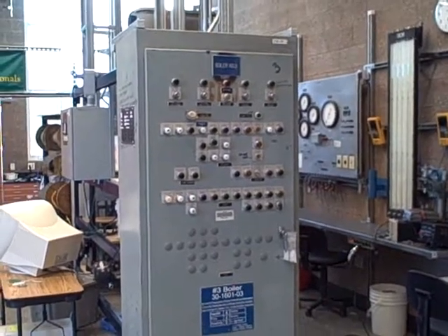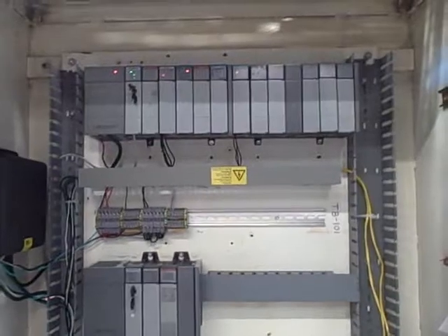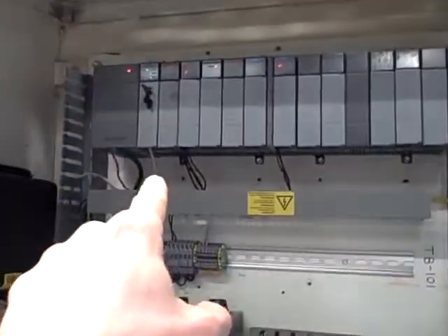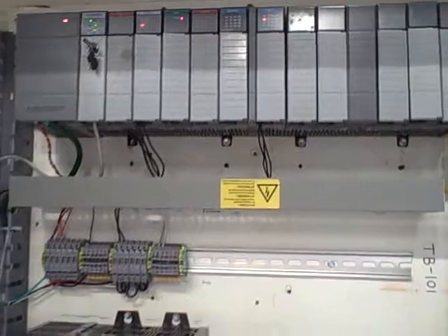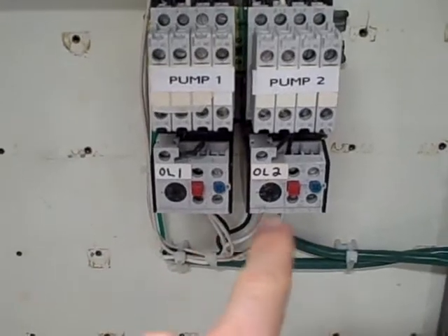It used to be part of a boiler control system, which is why it says boiler number 3 at the top. However, we have taken all the old controls out and installed an Allen Bradley SLC 500 PLC. Specifically, it's a SLC 503 processor, and we're using discrete inputs and outputs to control the statuses of 2 pumps. To control power directly to the pumps, we're using this pair of Siemens contactors with overload blocks here.